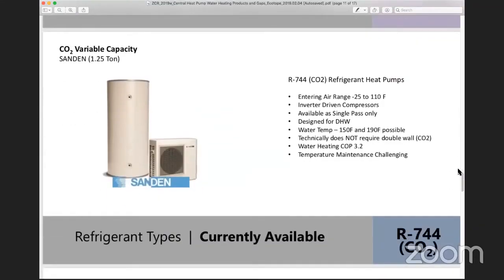Okay, next. This is R744, or CO2, as a refrigerant. This is a really high pressure cycle. It runs about 1400 PSI. This is the only currently available UL tested product on the market. It's on the smaller side at 1.25 ton, but we have had success ganging these up to 8 into a single loop, and so that's about a 100 unit apartment. That's the most we've done with these. They are single pass devices. They can make water up to 190, and the lab test for Northwest climate is about COP 3.2.